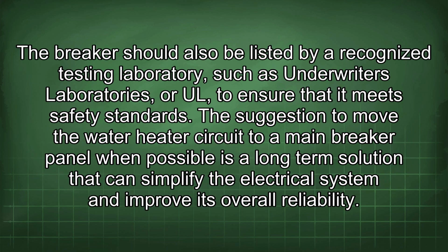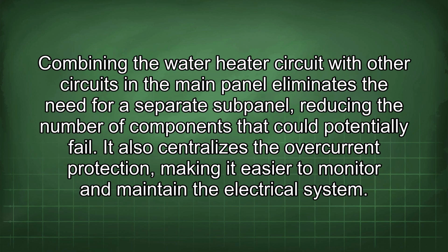The breaker should also be listed by a recognized testing laboratory, such as Underwriters Laboratories or ETL, to ensure that it meets safety standards. The suggestion to move the water heater circuit to a main breaker panel when possible is a long-term solution that can simplify the electrical system and improve its overall reliability. Combining the water heater circuit with other circuits in the main panel eliminates the need for a separate subpanel, reducing the number of components that could potentially fail. It also centralizes the overcurrent protection, making it easier to monitor and maintain the electrical system.